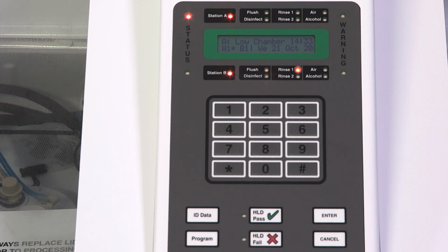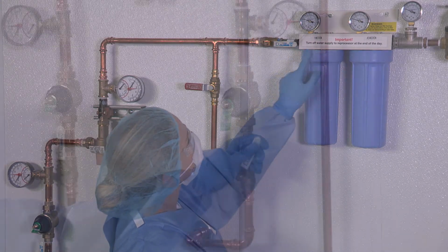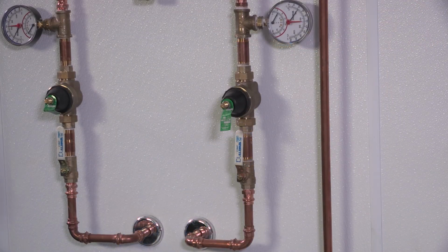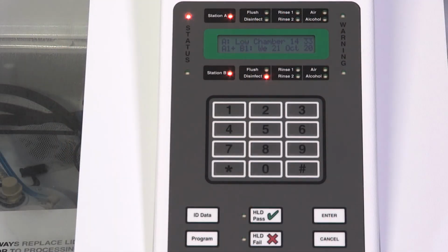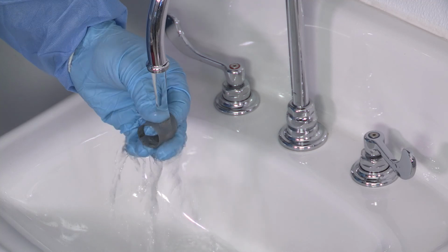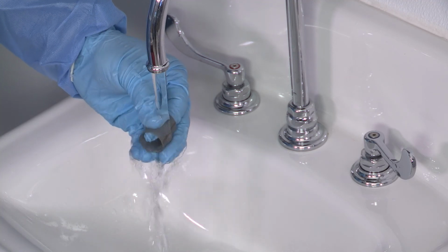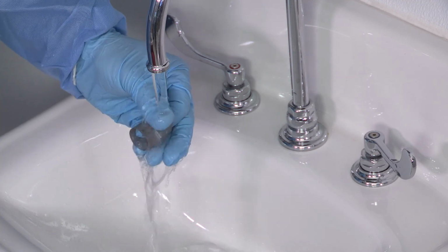Some issues could be the water filters may be clogged, and there is not sufficient flow and pressure. Inspect the pressure on the filter gauges. Or the water supply may be turned off. If alarmed in the disinfection cycle, the disinfection filter may be clogged. Cancel the cycle. Once the basin has reset, check the reusable mesh filter, clean as needed, and reinstall.